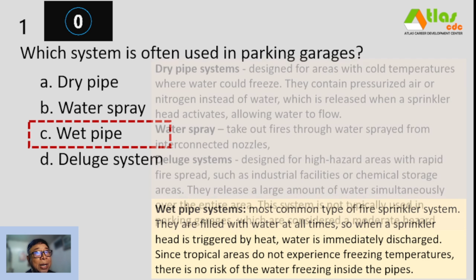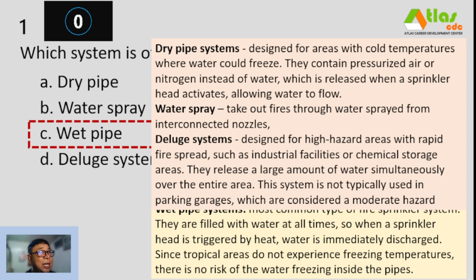Now, the dry pipe systems are designed for areas with cold temperatures where water could freeze. They contain pressurized air or nitrogen instead of water, which is released when a sprinkler head activates, allowing water to flow. A water spray takes out fires through water sprayed from interconnected nozzles, and deluge systems are designed for high hazard areas with rapid fire spread, such as industrial facilities or chemical storage areas. They release a large amount of water simultaneously over the entire area. This system is not typically used in parking garages, which are considered a moderate hazard.